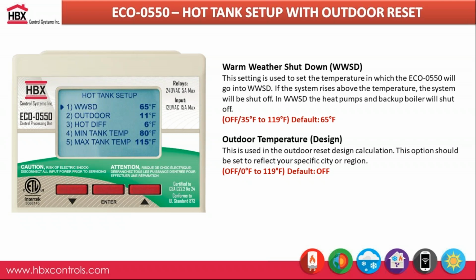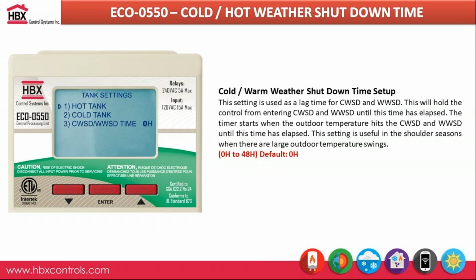And then again, you would put a differential on your tank for heating and cooling, and then you would just put min and max tank temperatures, and based off of outdoor reset, it will fluctuate between that min and max for outdoor reset purposes. We also have a lag time when it does get into cold weather and warm weather shutdown. So you can put a lag so it doesn't necessarily put the controller to shut off when it does go below or above those targets. We just do those for the shoulder seasons when there are large outdoor temperature swings. That timer begins when the controller goes into either warm weather or cold weather shutdown.